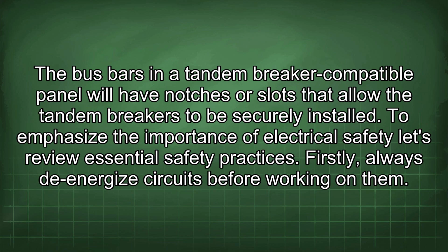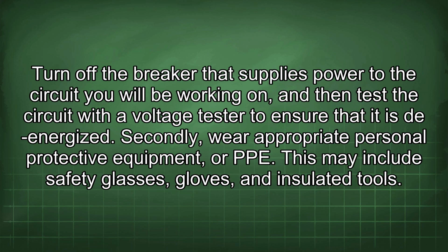Bus bars in a tandem breaker compatible panel will have notches or slots that allow the tandem breakers to be securely installed. To emphasize the importance of electrical safety, let's review essential safety practices. Firstly, always de-energize circuits before working on them. Turn off the breaker that supplies power to the circuit you will be working on, and then test the circuit with a voltage tester to ensure that it is de-energized.